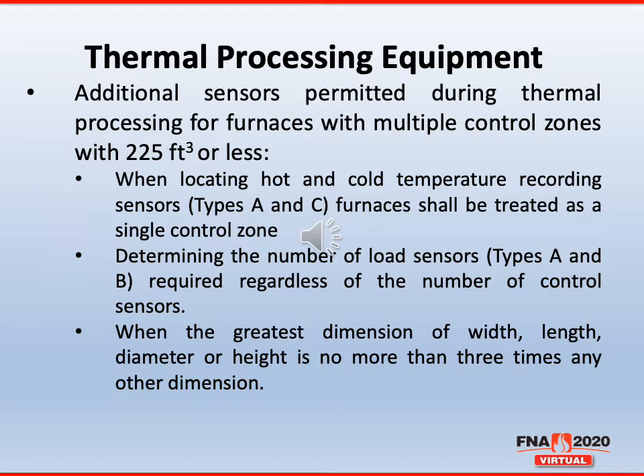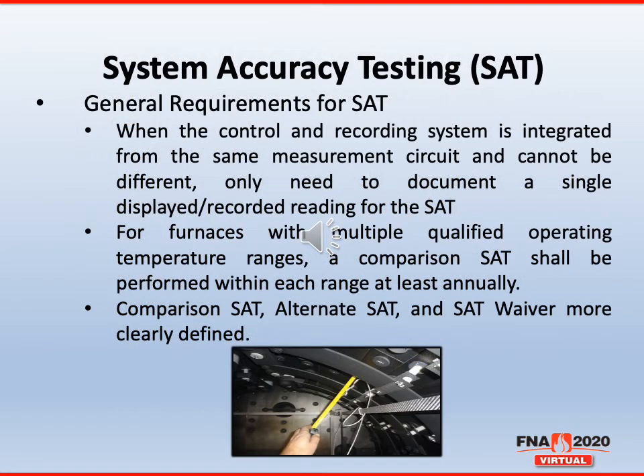So anything that's 225 cubic feet or less that has multiple control zones can be treated as one single control zone. For those that are larger than the 225 cubic feet, as long as the greatest dimension of width, length, and diameter or height is no more than 3 times any other dimension. If it is, then other sensors will be required.